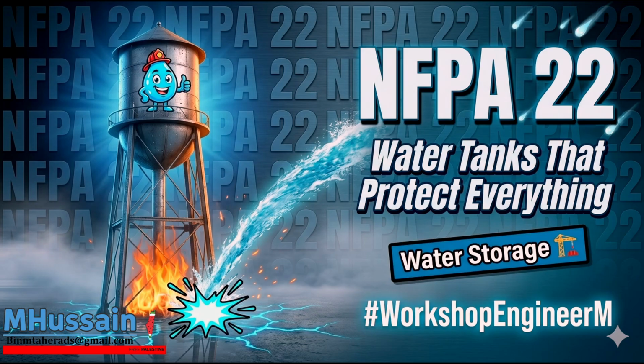It lays down a very strict legal and engineering baseline. It explicitly states that the adequacy and dependability of the water source is of primary importance. But, I mean, what does primary importance actually mean when you're sitting down to design a system from scratch? That's the question. It means the NFPA committee is explicitly warning engineers not to make assumptions about municipal infrastructure. If the city water isn't adequate, whether that deficiency is in quality, quantity, pressure, or just historical reliability, you have to engineer an alternative. A dedicated source. Yeah. You can't just specify tap into a city main, run your hydraulic calculations based on, like, a single flow test performed on a random Tuesday morning and call it a day. No, the standard requires proof of dependability.